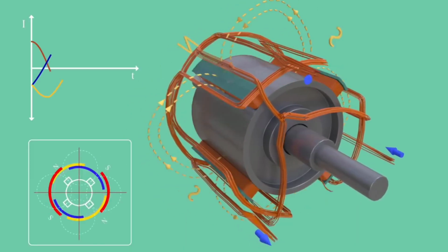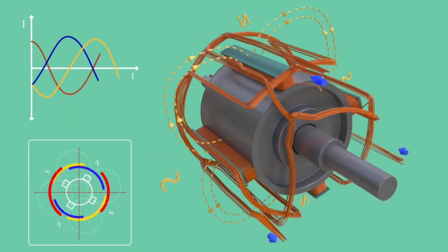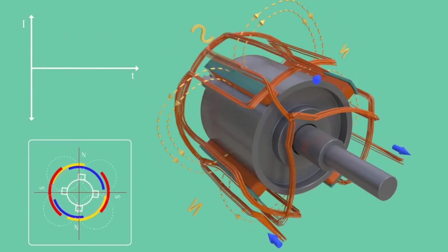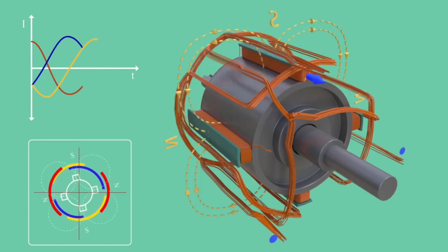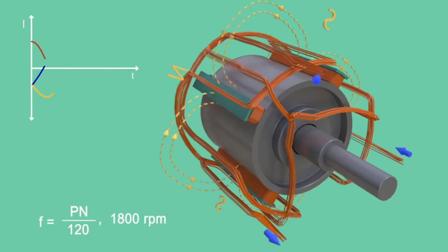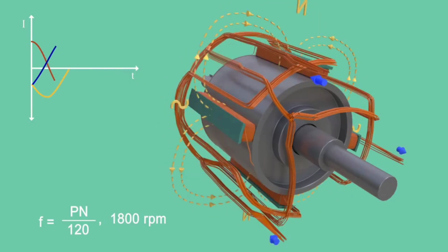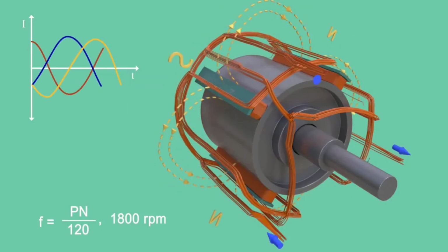It is clear from the past equation that in order to produce 60 Hz electricity, a 4-pole rotor should run at the following speed of 1,800 RPM. Such huge RPM will induce a tremendous centrifugal force on poles of the rotor and it may fail mechanically over time.